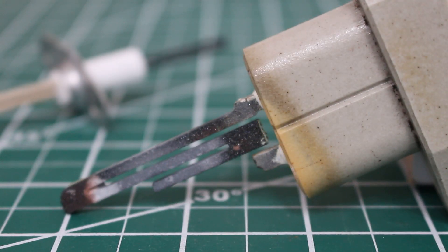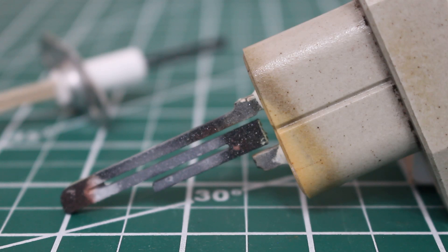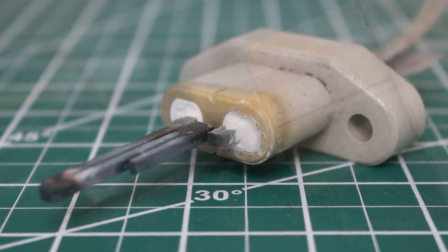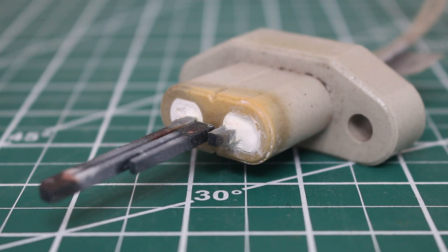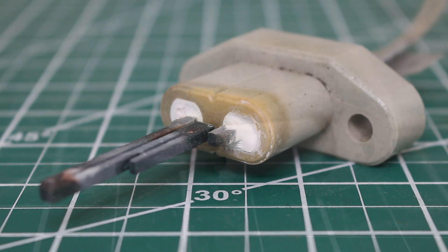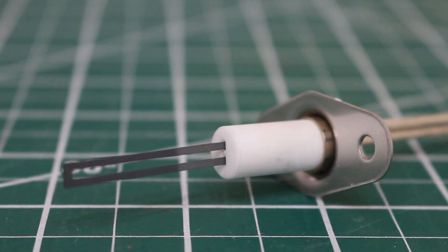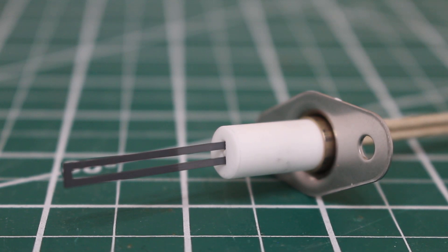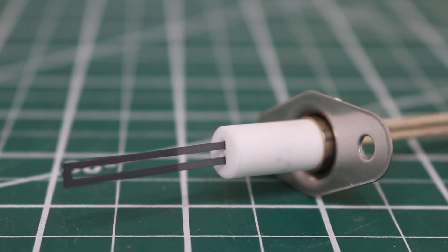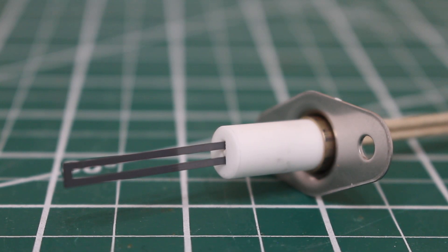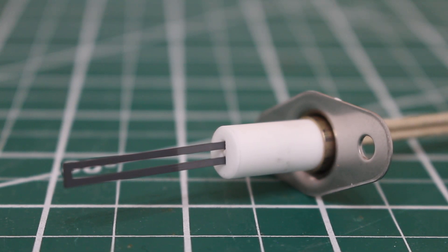Hot surface igniters are most commonly used in electronic ignition systems. The two composition materials generally associated with hot surface igniters are silicon carbide and silicon nitride. The hot surface igniter shown here specifically is silicon carbide which is a compound of carbon and silicon. This hot surface igniter here specifically is a proprietary ceramic composite but it is very similar looking to the silicon nitride which is a chemical compound of silicon and nitrogen. They are typically smaller and more durable.